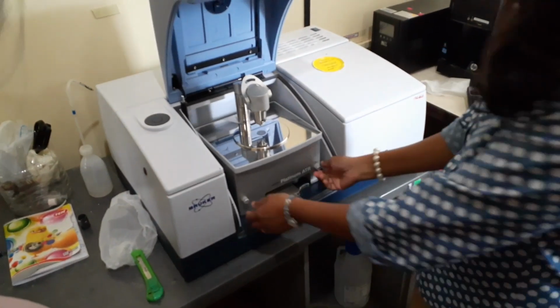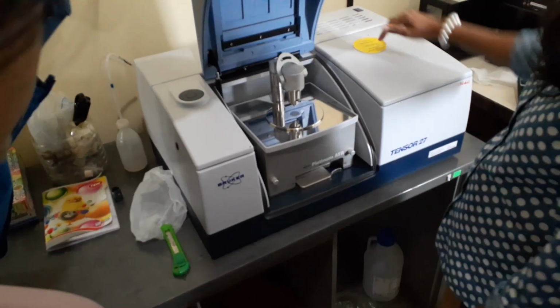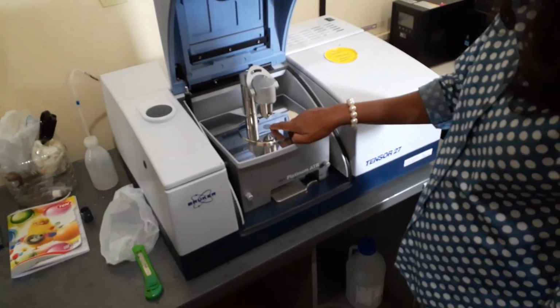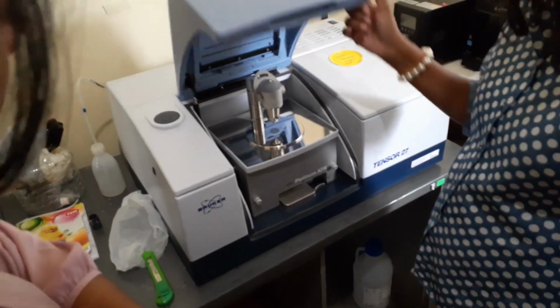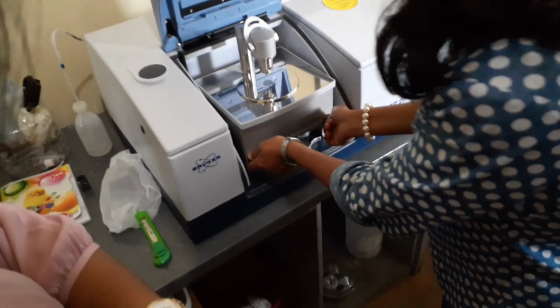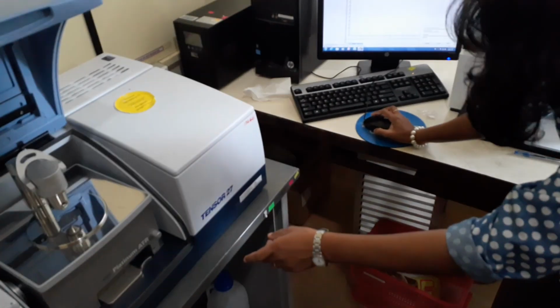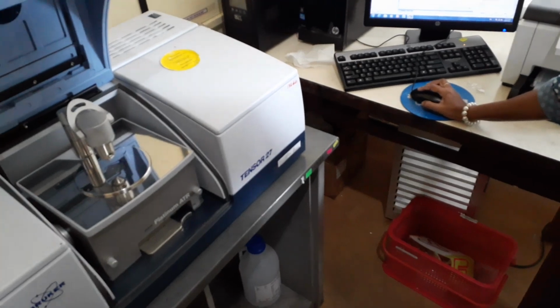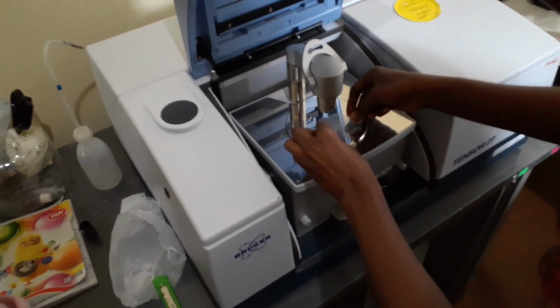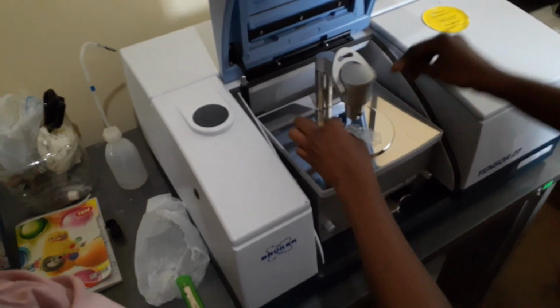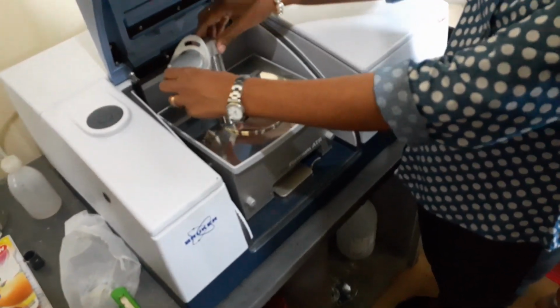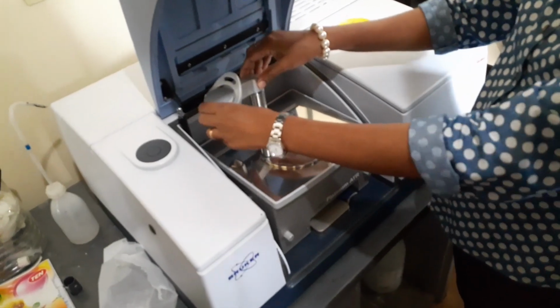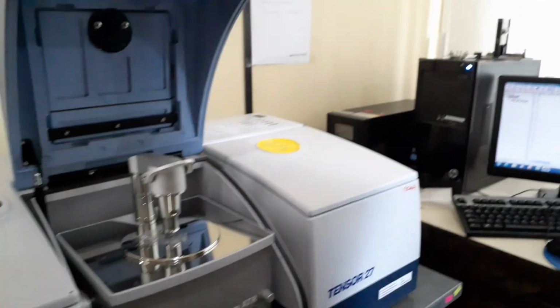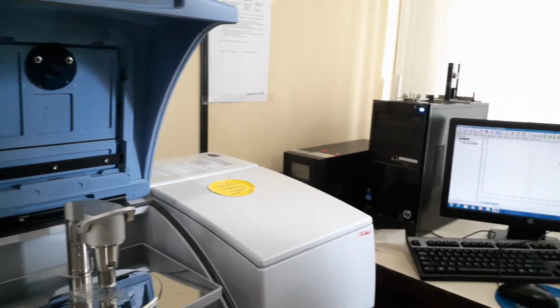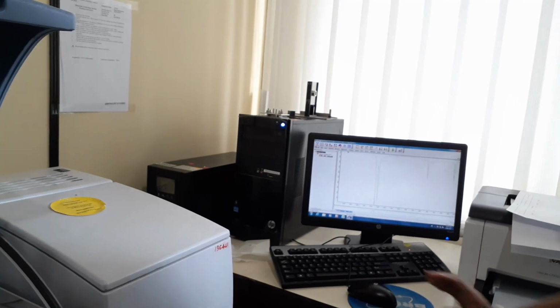Now let's switch to the ATR compartment. We'll analyze the same polyethylene sample, this time using ATR mode. Just as before, we'll select the appropriate measurement parameters for ATR mode and start with a background measurement. Once that's complete, we can load the sample and proceed with the measurement. When the ATR measurement is finished, we'll have a new spectrum which we compare with the spectrum obtained in transmittance mode to observe any differences.